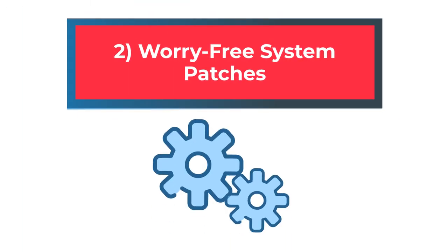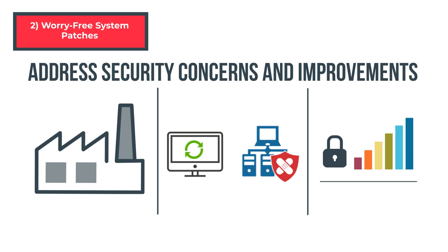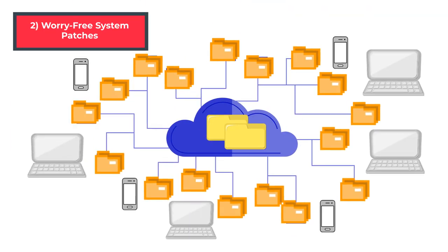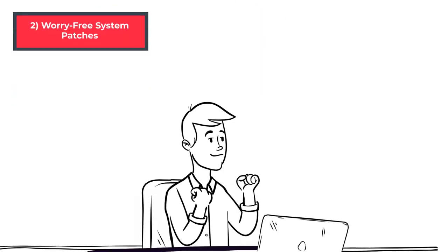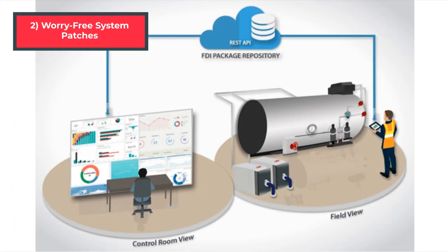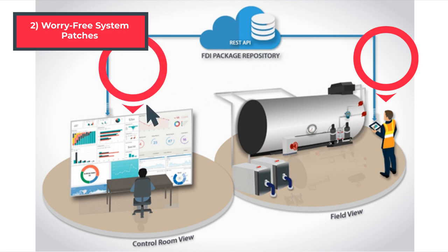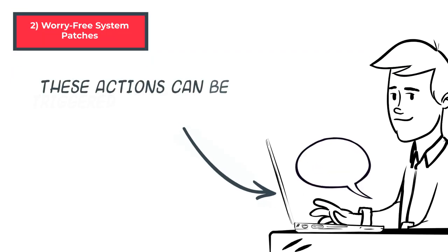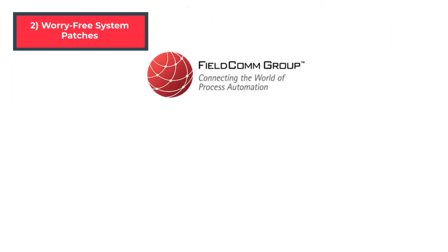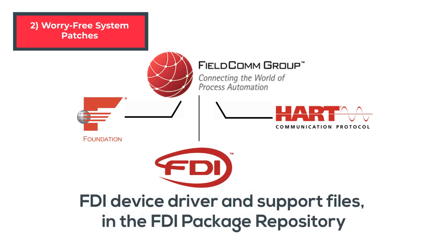Benefit 2: Worry-free system patches. Throughout the lifetime of systems, occasional patches and upgrades are required to address security concerns and improvements. The FDI Device Package Repository can automatically download appropriate EDD and FDI device packages when patches or upgrades are completed, which saves time and effort. During device replacement or upgrade, a built-in FDI package update module in the host application or handheld communicator will securely connect to the FDI package repository. On successful connection, it will search the repository and download the appropriate package version onto the system. These actions can be triggered on-demand or automatically to keep the system up to date. FieldComm Group maintains the API as well as registered Foundation Fieldbus, HART, and FDI device driver and support files in the FDI package repository.